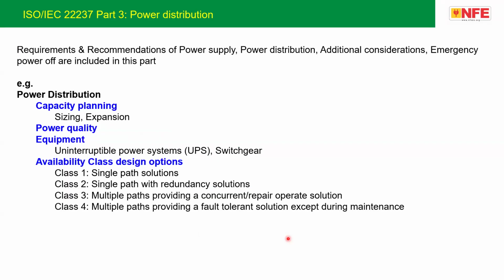Now when we move from power supply to power distribution, in power supply we discussed how we get the supply from the main grid or main power source to the facility. Now we move to power distribution, where we distribute the power within the facility. First again is the capacity planning of the data center. The maximum capacity of the power distribution system and the associated space of the data center shall be sized to accommodate the maximum planned IT load, the future requirement, and technology development also. Additional load, including but not restricted to security, lighting, and UPS battery recharging, is required during the battery discharge time. Next, during operation time, we have to take care of the initial load, what the day one load will be, and the growth of active load over time for the data center.